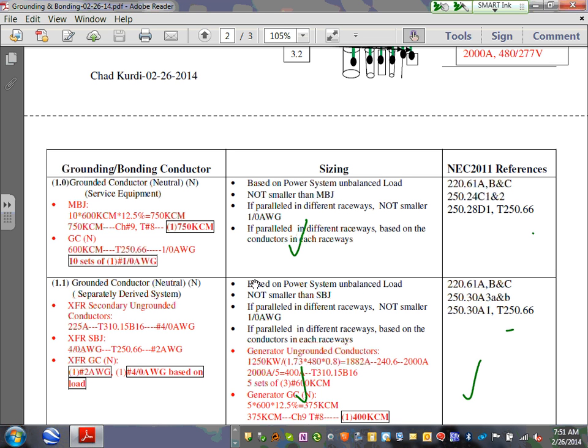Number 1, based on the power system unbalanced load. Number 2, not smaller than the main bonding jumper. Number 3, if you parallel, you can't go less than 1 aught. And number 4, if you put them in different conduits, you base the conductor, the neutral, on the conductors in that particular conduit. Matt, does it make sense? This is how you size the neutral at the service. This is how you size the neutral at the service, John.